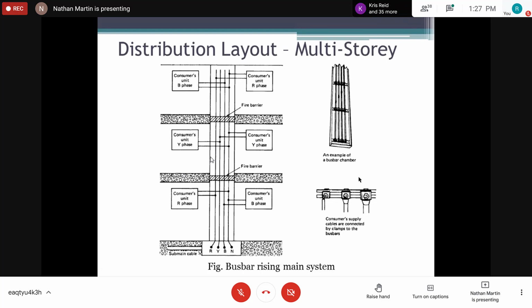Because in every installation, you would have to have a panel box in every dwelling, right? So you can't have one panel box that controls the entire floor. That doesn't make any sense, because I should be able to disconnect my supply, right, without disturbing the other customers. The other customers should be able to disconnect their supply without me disturbing them. And this is basically in a situation like a building where we have different floors that deal with different aspects. Each floor should also have its means of isolation, right? So they'll have their consumer or their panel box that disconnects that particular floor.